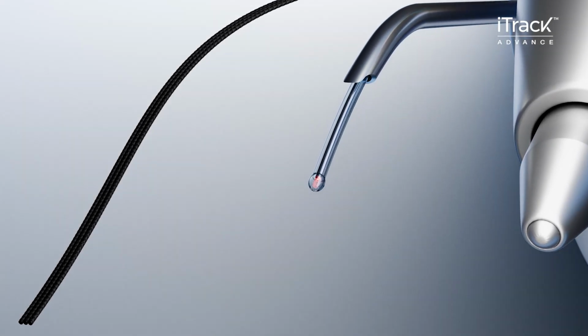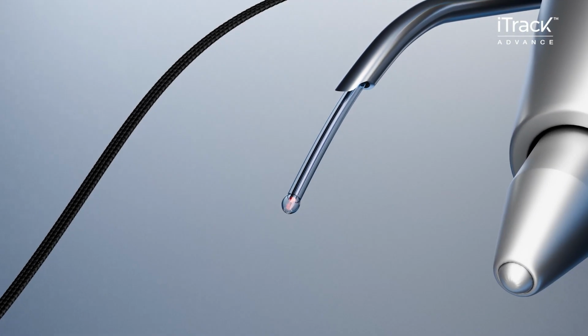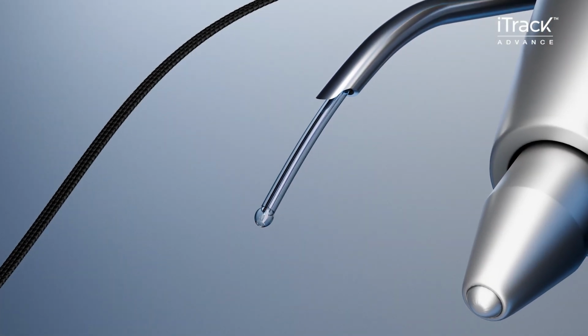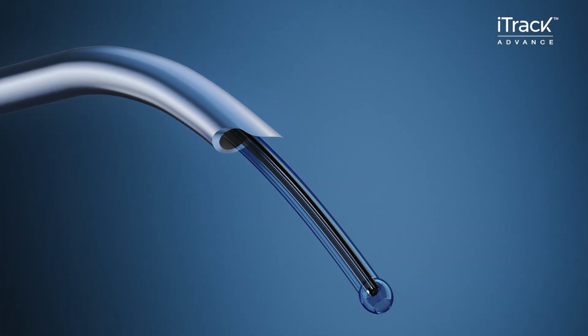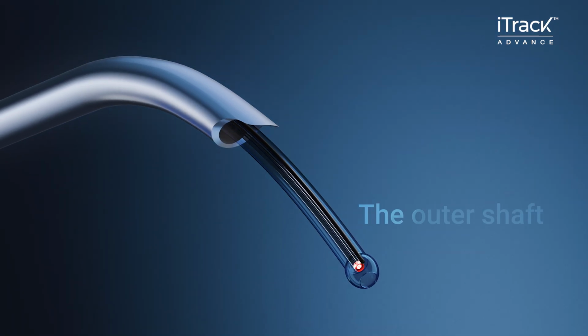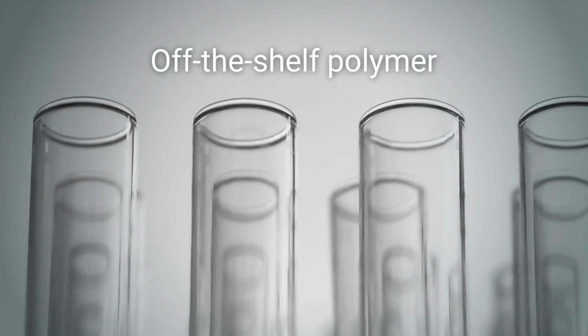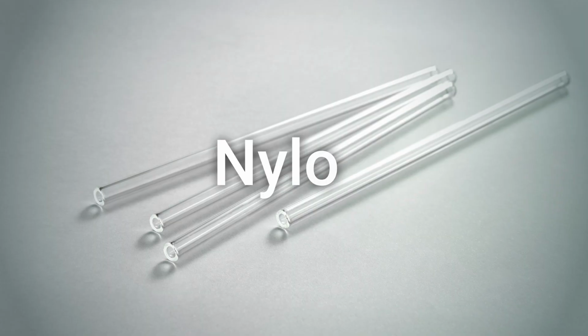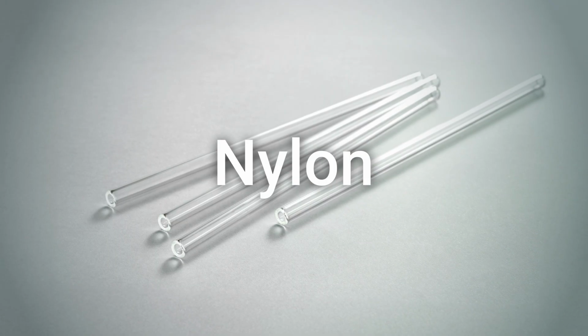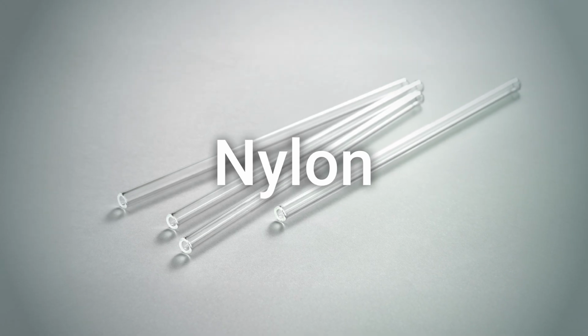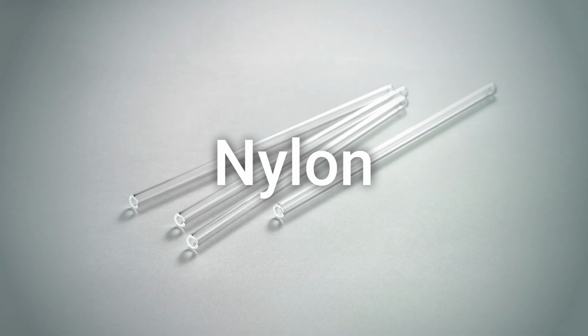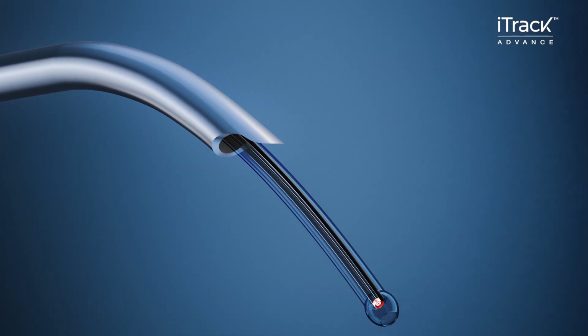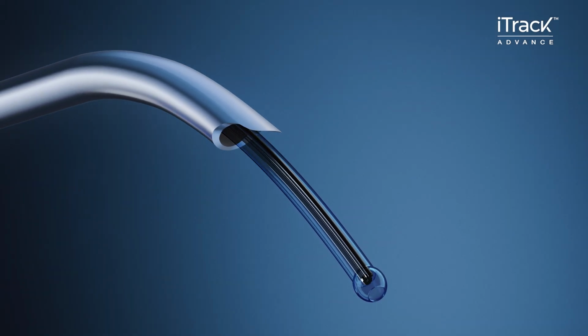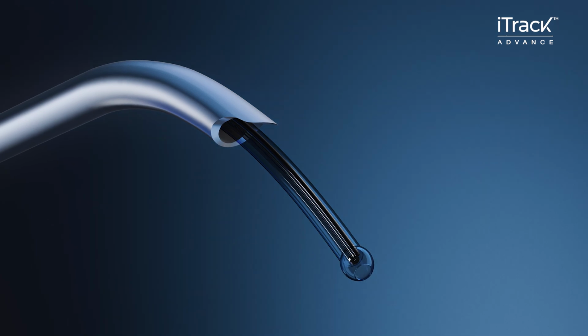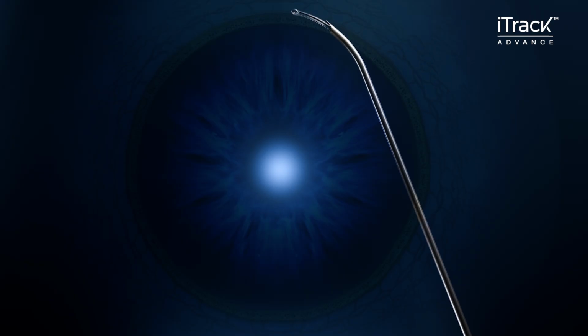But the real engineering feat isn't just making something small, it's what's packed inside this micron-sized catheter. So how do you achieve that? The answer starts with the catheter's skin. Now, if you're making a standard catheter, you might reach for an off-the-shelf polymer like nylon. It's a workhorse material, it's strong, and it gets the job done for a lot of applications. But canaloplasty puts extreme demands on a material. You need toughness to protect the delicate inner workings, but you also need flexibility for the 360-degree journey.